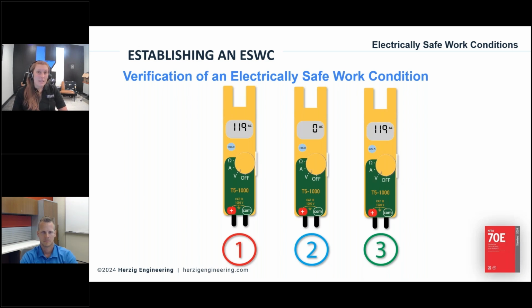If you get a drastically different reading or no reading at all, that's a sign that your meter has malfunctioned and you should not trust that 0 was actually 0. Okay, so I know a gentleman personally that this saved his life. He was troubleshooting a piece of equipment. He figured out what was wrong with it. He went to shut it off. It was funny, the only outlet in the room was being used for a couple of box fans because it was so hot in there. And so he unplugged one of the fans and did his voltage check, and he got what he expected for an outlet. He plugged the fan back in.